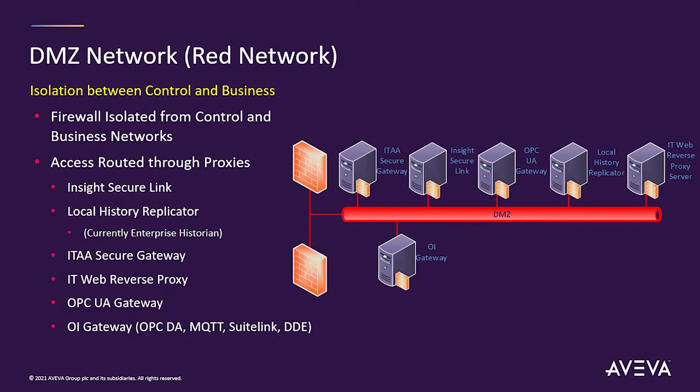There should be a DMZ on top of the process control network — that's what my process control network talks to, not directly to the business network. I can put all the interfaces I want other people to use in the DMZ: they can get into the DMZ but not into the process control network. A properly designed OT environment should not have the internet on the other side of a single firewall. There should be multiple firewalls — NERC CIP even says two different firewalls made by two different vendors, so if someone breaks into one you can protect against them getting all the way through.